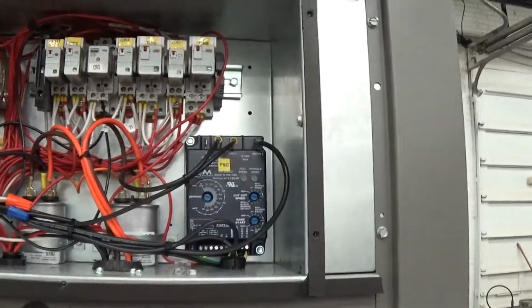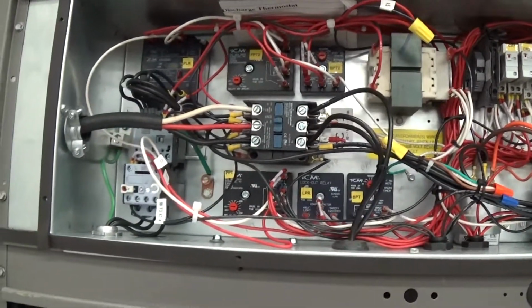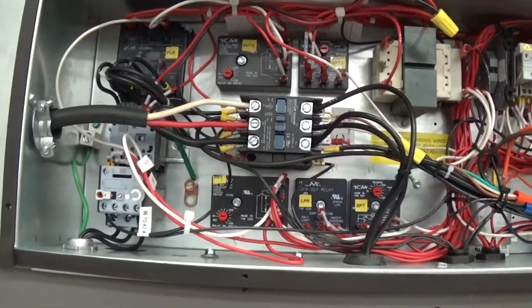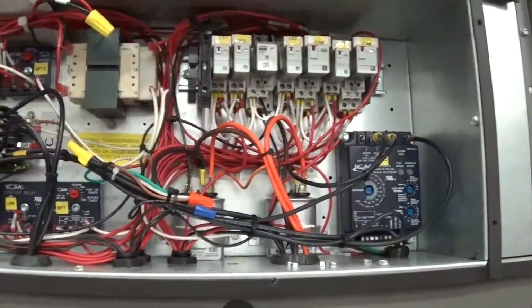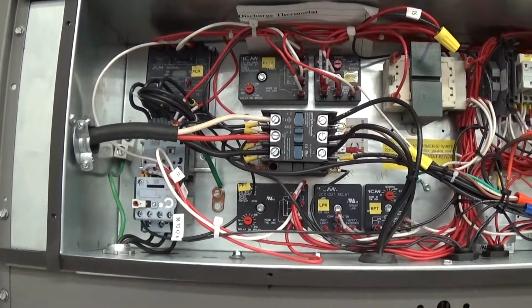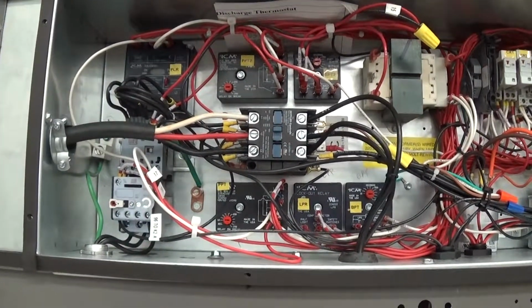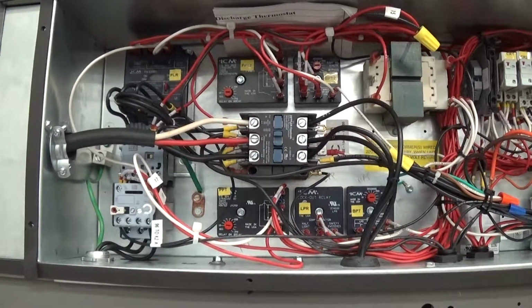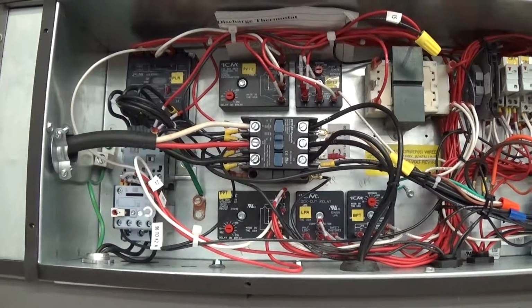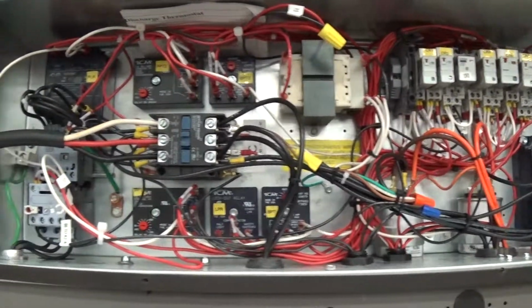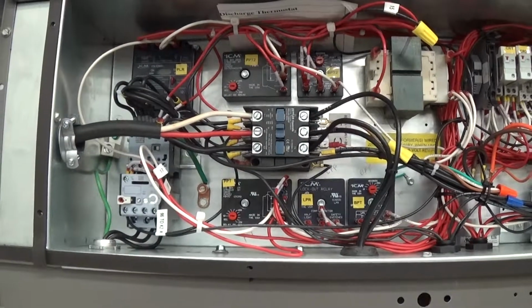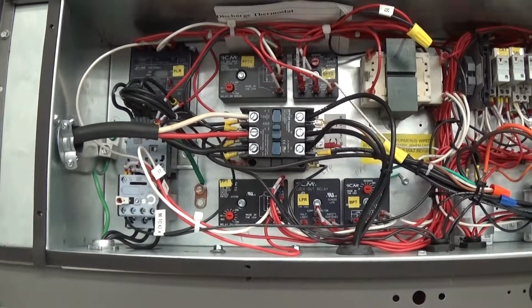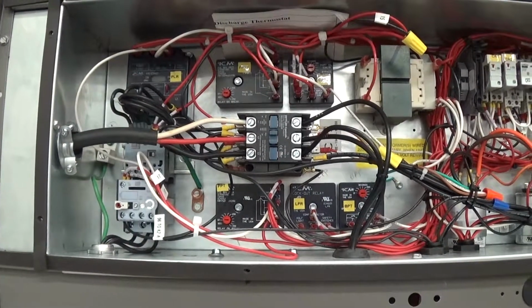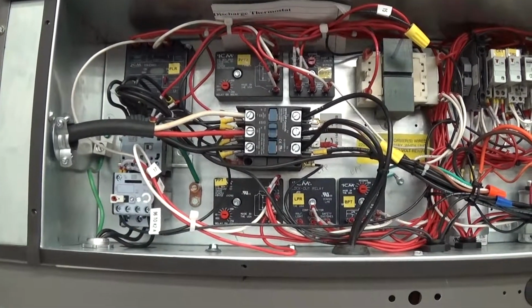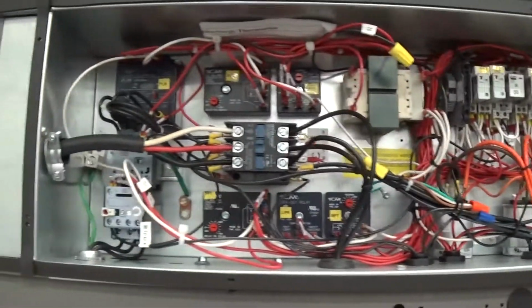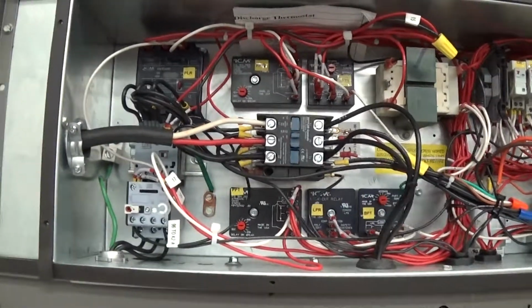Here we have all our controls and our relays. This unit has some fairly sophisticated timers and bypass timers and such to achieve a couple different things. One of them is a low pressure bypass on startup in a cold environment. That'll ignore a low pressure situation for a certain period of time, so you don't get any nuisance trips. There's also a minimum run time timer. Copeland has a minimum specification on how long the compressor should run to avoid too many cycles, too many starts. It also has that in there with those adjustable timers. You shouldn't need to adjust any of those.